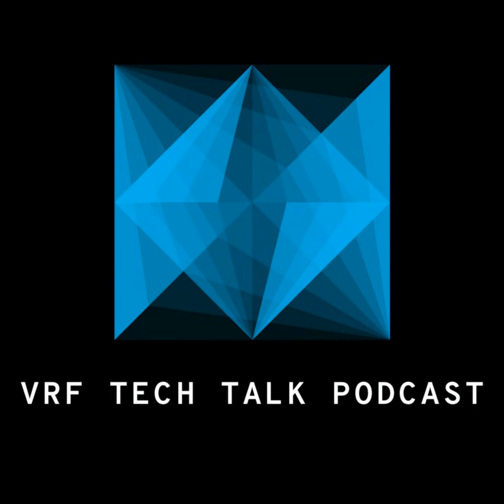I did a symposium presentation this year, the HVAC symposium. Huge shout out to HVAC School there. I talked about communication and data packets, not just for Daikin, but for all communicating equipment. Those ones and zeros, that binary code, are carried on a carrier wave, and that carrier wave is 16.5 volts DC. If you add a bunch of resistance or long wire lengths to the system, you're naturally going to drop that carrier wave. And when that carrier wave voltage drops, of course the data packets don't make it either. The signals aren't as strong as they should be, you lose data packets along the way, and then the U4 generates.